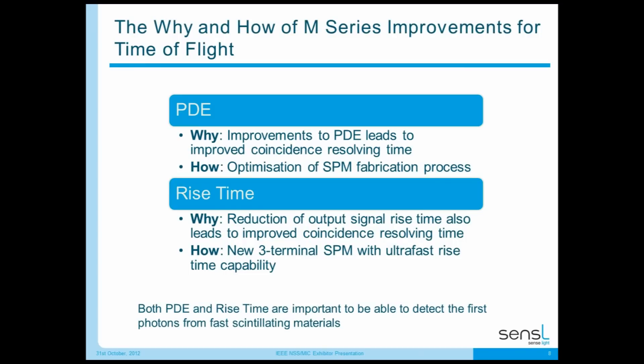To explain why and how the M-Series improves time-of-flight detection: there are two things you need to work on — PDE and rise time. Improving PDE leads to improved coincident resolving time because you can detect photons better. You optimize the SPM fabrication process and device, which SensL has done. Reducing the output signal rise time also improves coincident resolving time. SensL created a new three-terminal SPM with ultra-fast rise time capability. Improved PDE combined with improved rise time can lead to very good timing measurements.